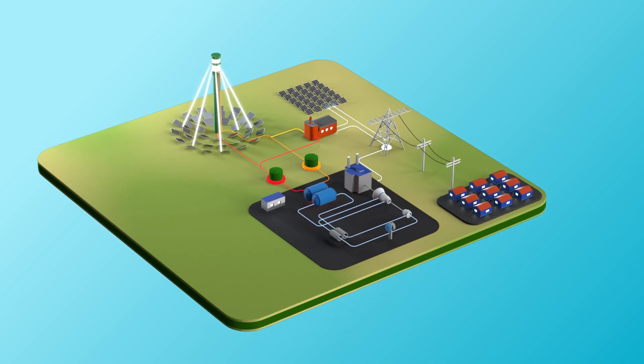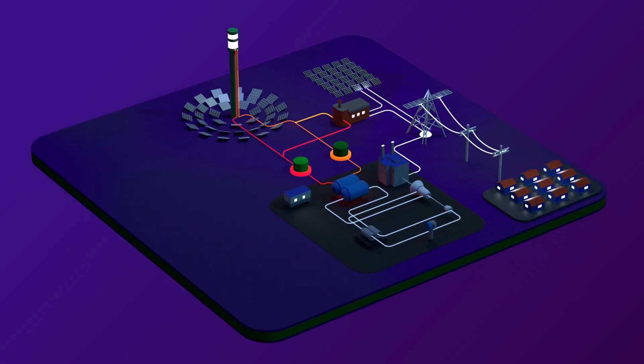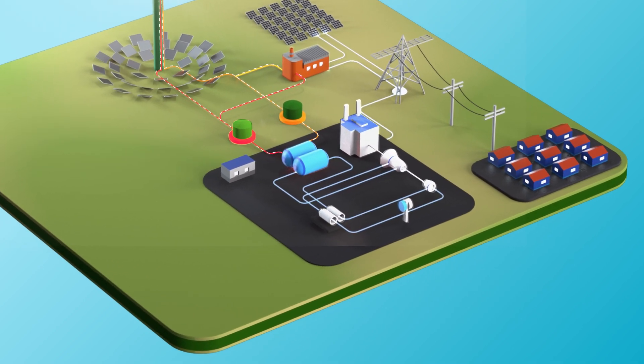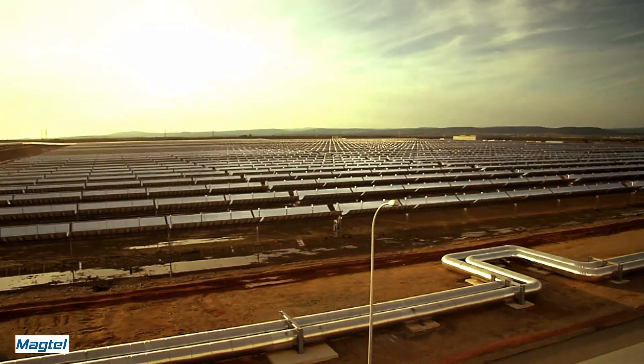In a hybrid PV and CSP SCO2 system, solar energy is collected by mirrors and concentrated onto a receiver situated on the top of a tower, where molten salts are heated and stored in tanks, enabling the plant to provide heat for power generation on demand, day or night. If needed, and in case of excess PV, an electric heater can be used to boost the temperature or to increase the flow of molten salts. This stored heat is then used to drive a supercritical CO2 power cycle via a tailor-made molten salt CO2 primary heater. The La Africana project will be one of the first megawatt-scale SCO2 plants in the EU.